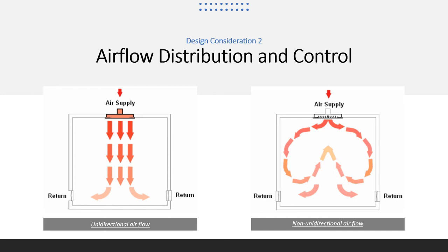The unidirectional airflow pattern is a single-pass, single-direction airflow of parallel streams. It is also called laminar airflow. Unidirectional clean rooms are used where low airborne contaminant levels are required and where internal contaminants are the main concern. They are generally of two types. Vertical downflow clean rooms, where the airflow is vertical laminar in direction, and horizontal flow, where the airflow is horizontal laminar in direction.